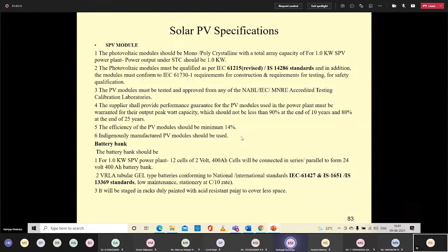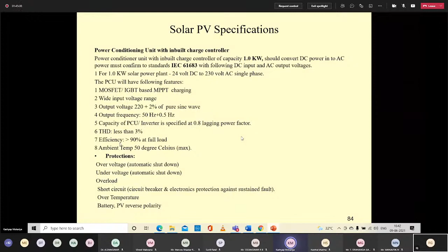For the power conditioning unit, I have to know the norm IEC 61683. I have to specify that I want MPPT charging. It should be an inverter with a pure sine wave. The tolerance I have to mention here. I have to mention the capacity of the PCU at the power factor. I have to mention the protection, as I mentioned in the slide, that what sort of protection is actually required.